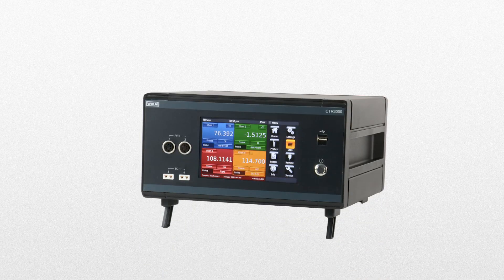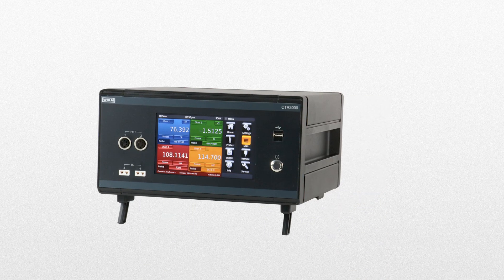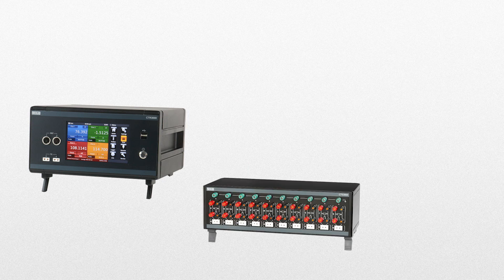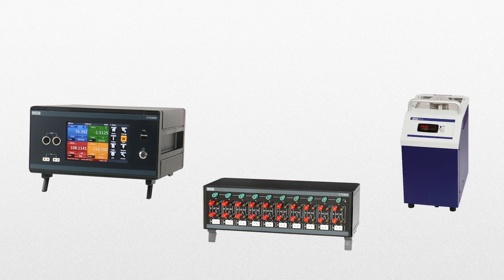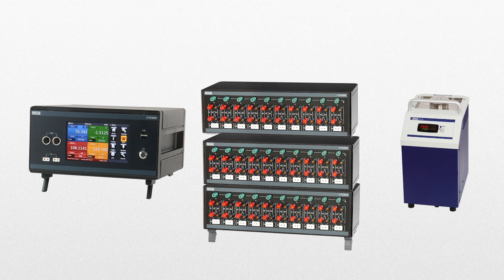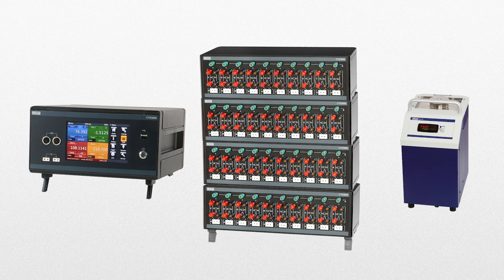When used together, WIKA's CTR3000 Multifunctional Precision Thermometer, the CTS3000 Multiplexer, and the CTB9100 Temperature Bath provide a complete temperature calibration system, capable of measuring, scanning, and calibrating up to 44 probes at a time.